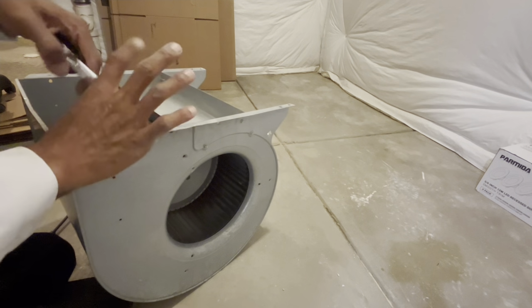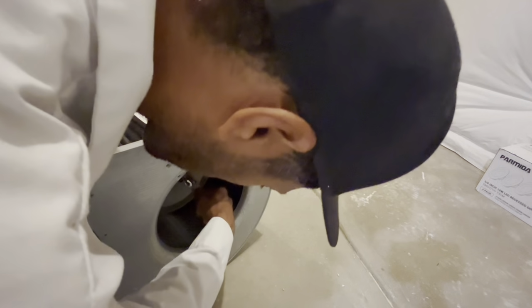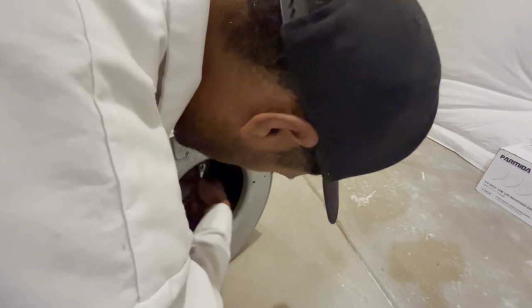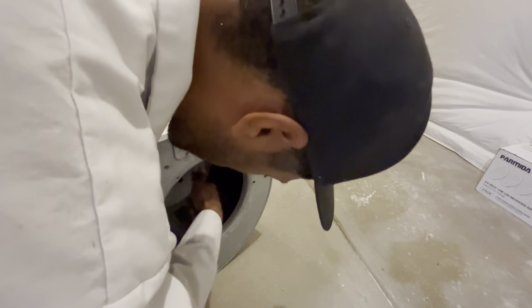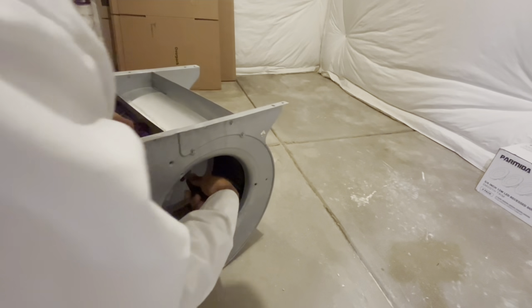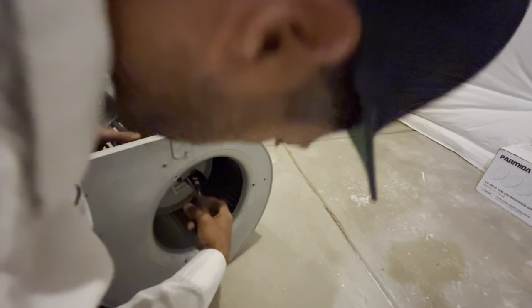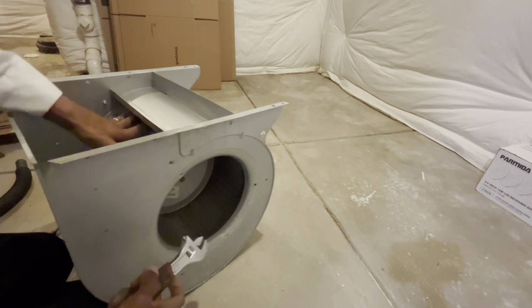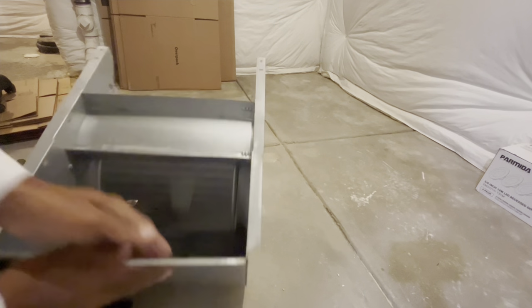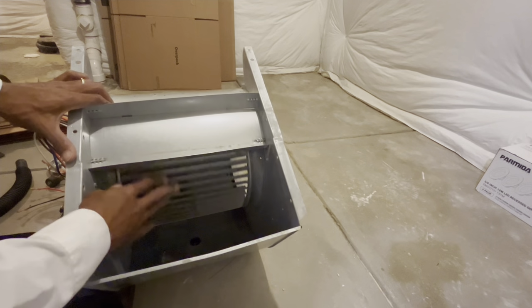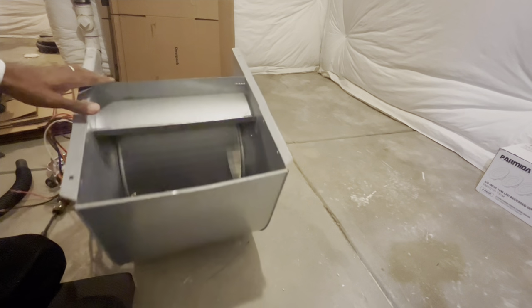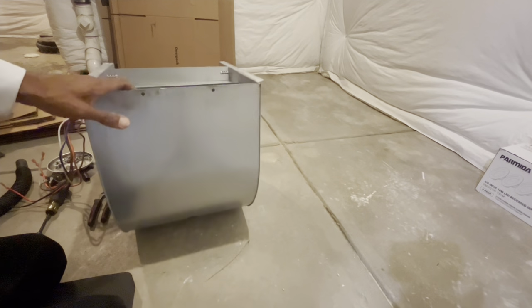So now that the motor's been mounted to the wheel, making sure that I'm lining up the actual wheel inside the housing has to be centered in there. That way when it's actually running and spinning and moving air, that it's not going to hit the sides of that housing in a sense. And you have a set screw, so basically you can take a crescent wrench and tighten up that set screw, so that way it's not going to come loose. And I also do a spin test.